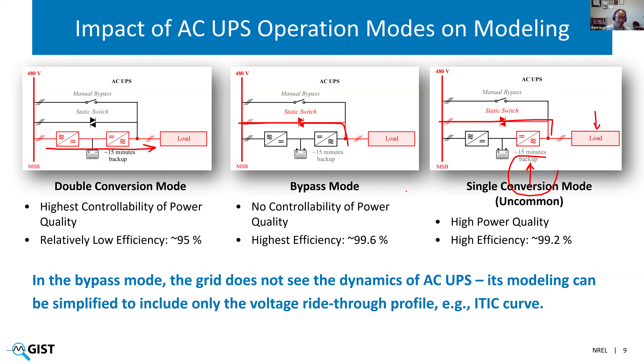There's a third mode. I don't think it is very commonly used, where the UPS is bypassed, but the load side converter is still active to provide power quality, in which case we need to focus on both the modeling of IT racks or PSUs within the load, as well as this load side converter in the AC UPS.